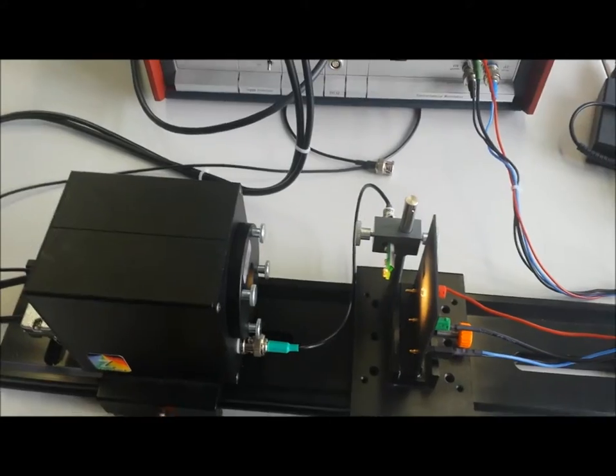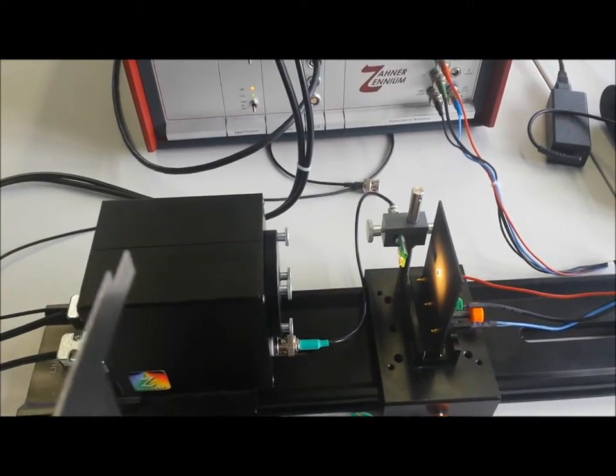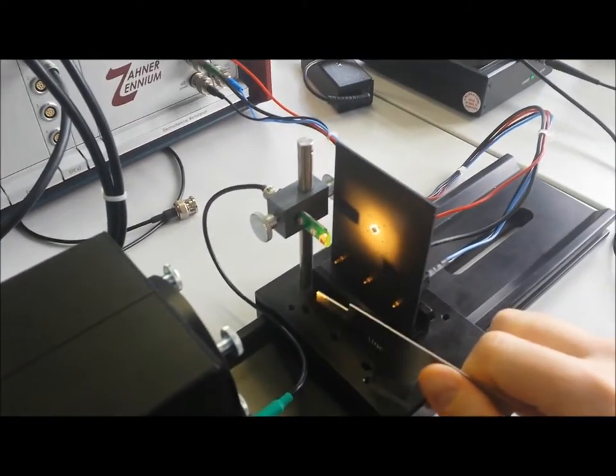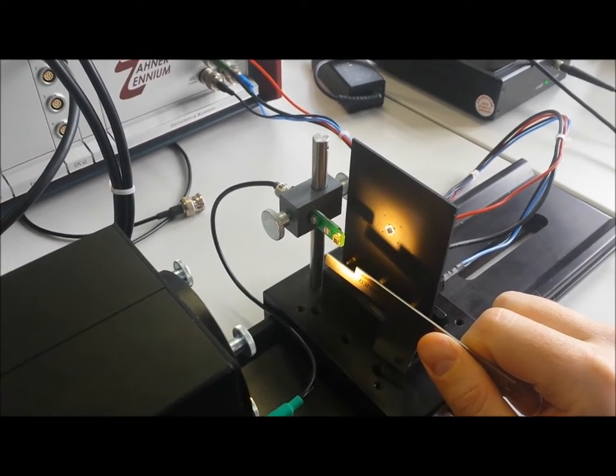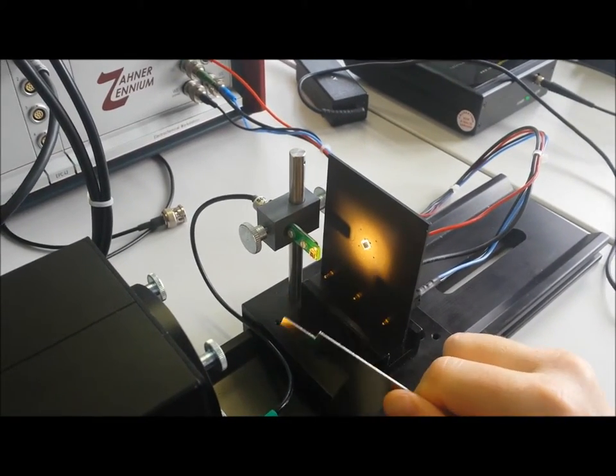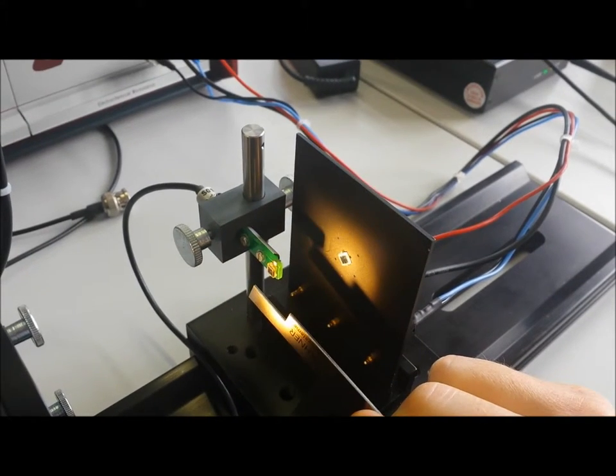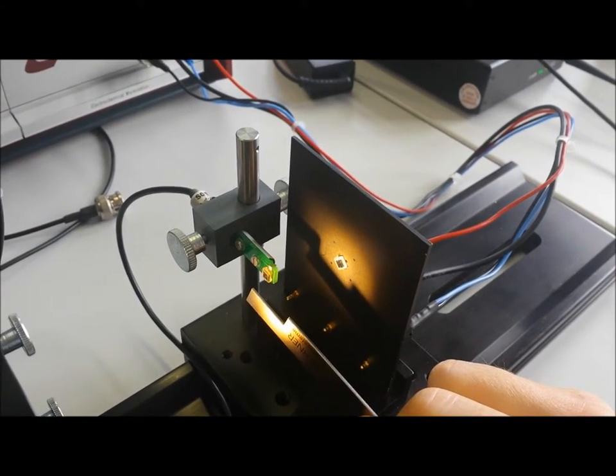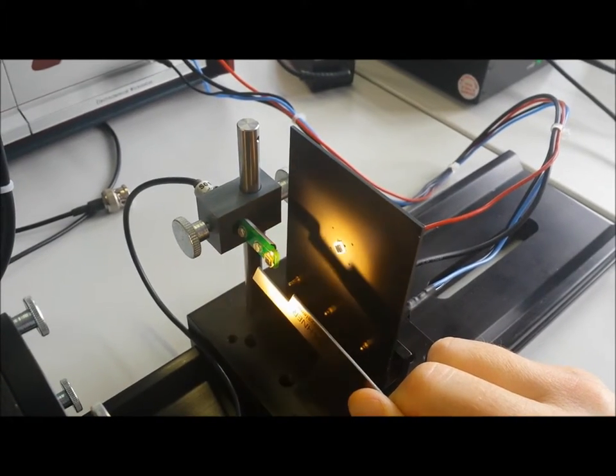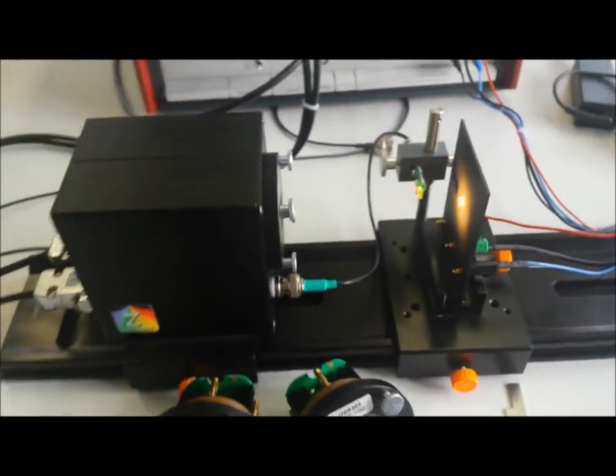What I'm going to do is take a little tool and start occluding or blocking the light that reaches the sensor. I want you to watch the intensity on that light. It's hard to see by video, but I'm deliberately putting a shadow across the sensor. The sensor now thinks that there's not so much light being transmitted and forces the light source to apply more light to give you the intensity that you're asking for. There it goes brighter.